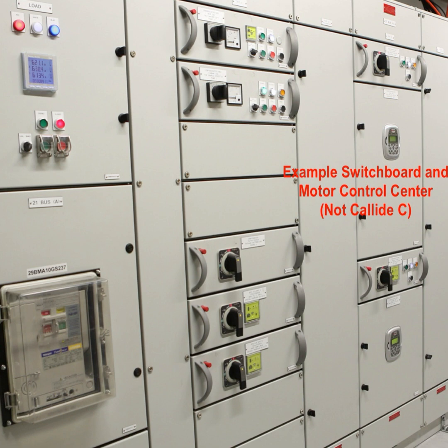So let's start at the 6.6 kV feeds first. The 6.6 kV supply goes through a step-down transformer to feed the 415-volt bus, and these both power multiple critical subsystems, including the 220-volt DC battery chargers, the generator seal oil pump's primary supply, and lubrication oil pump's primary supply, amongst several other things. These tripped 2 seconds after the station interconnector on the DC bus was opened. They tripped on arc flash protection. So for those that aren't electrical engineers, what does that mean?